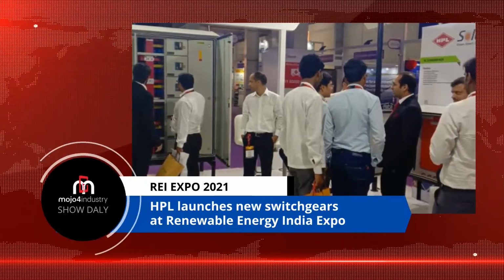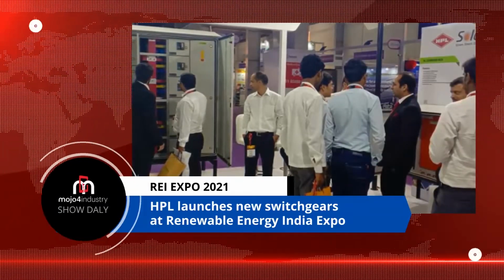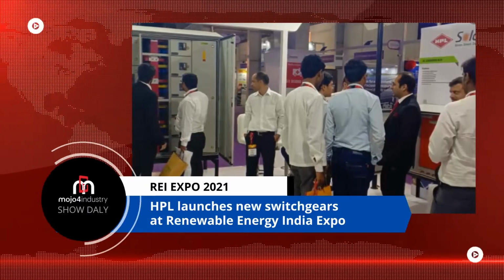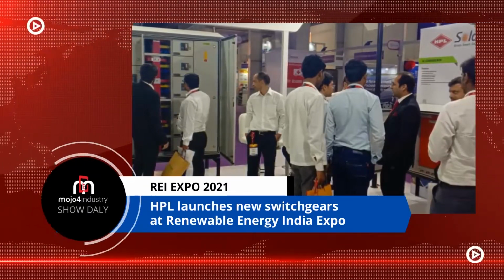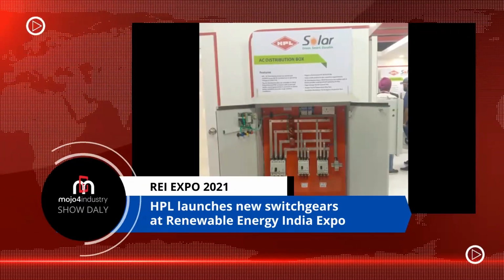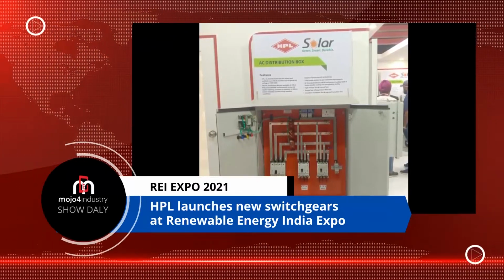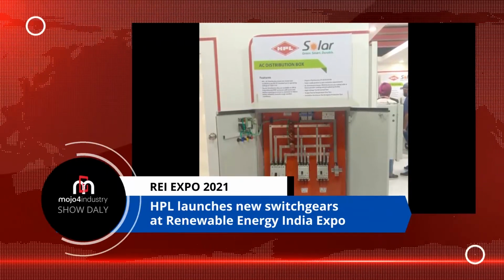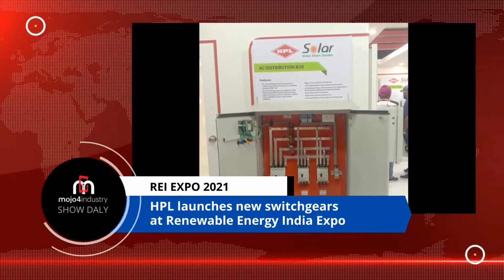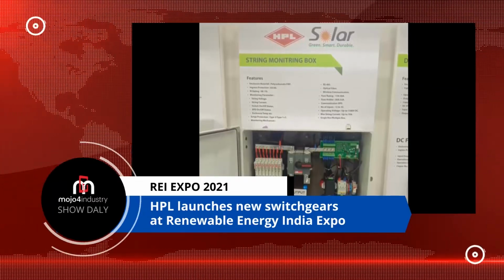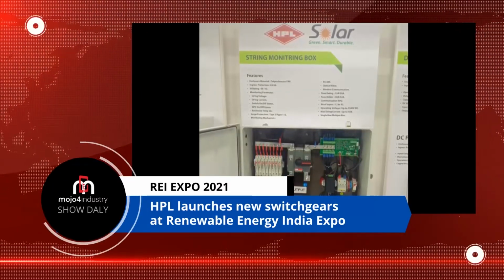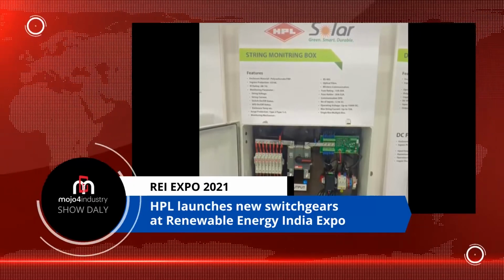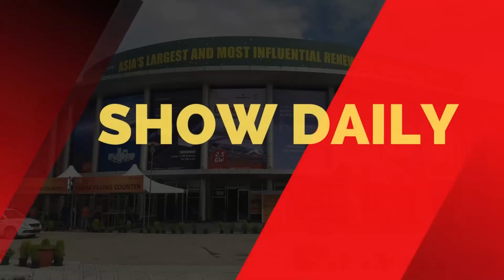The new DC disconnectors are built particularly for PV applications and are very robust and long-lasting. They have a rated voltage of up to 1500 volts DC and can be utilized in PV power systems. They provide safe electrical isolation in the presence of arc chutes to avoid chances of hazards due to arcs developed in DC circuits. The switches make and break quickly under load conditions.